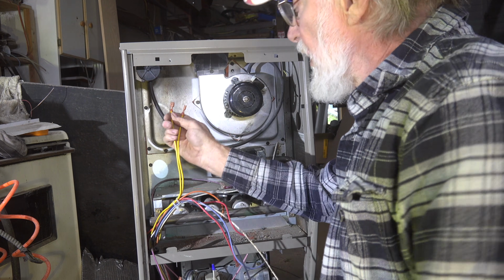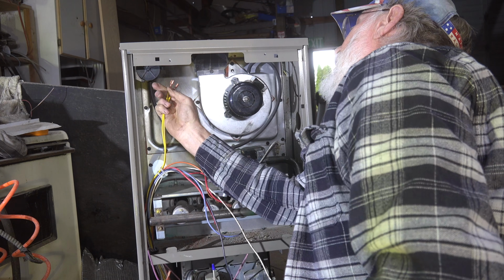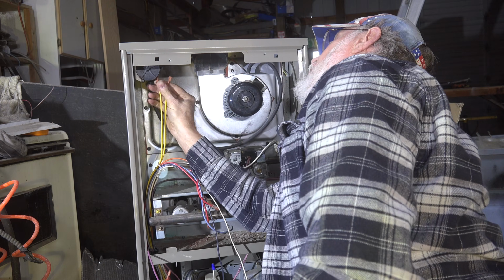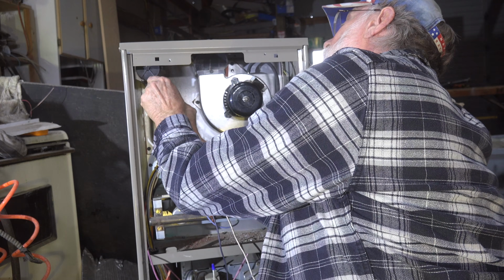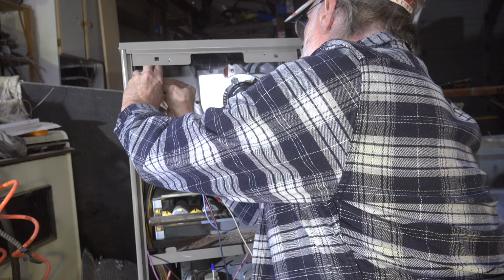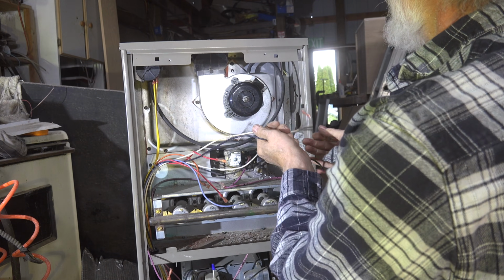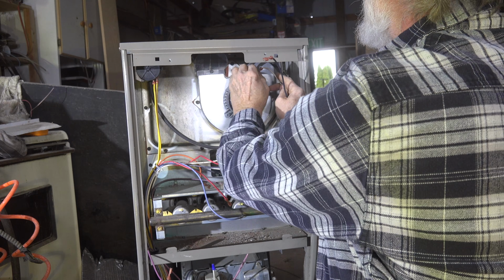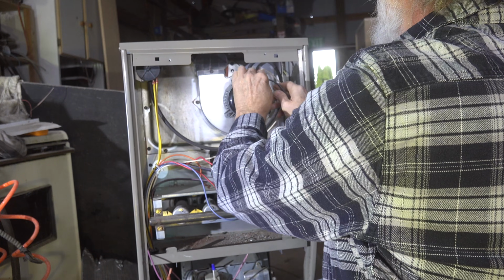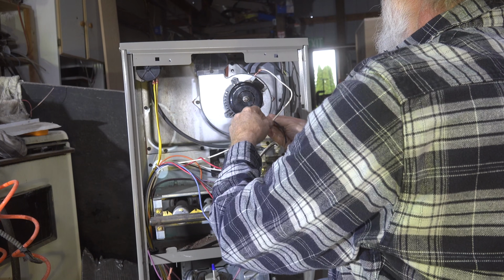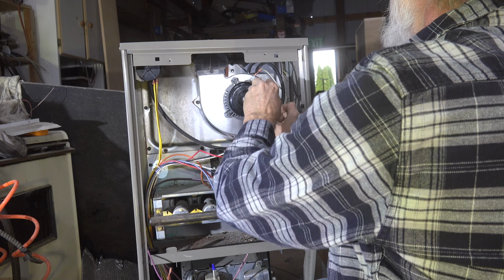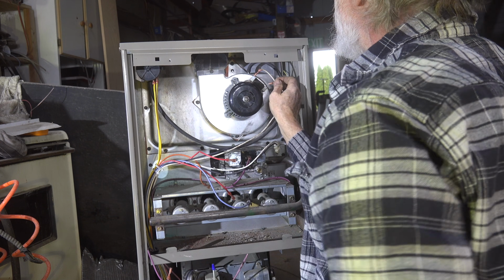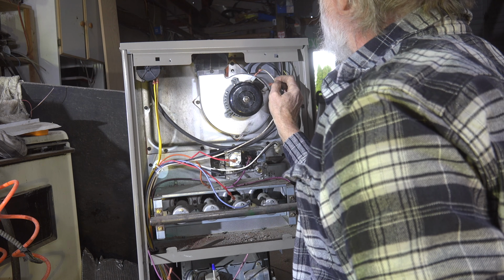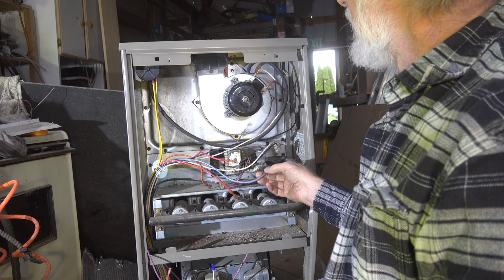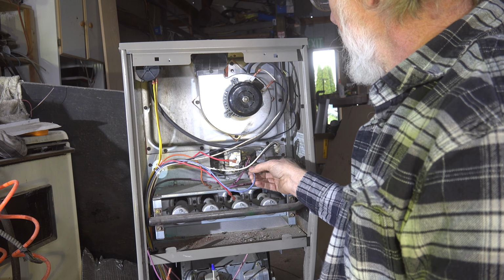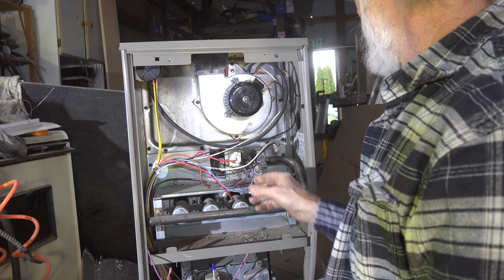The two yellow go to the pressure switch. Doesn't make any difference which one goes where. Black and white, they go to the inducer. Again, it doesn't make any difference which side they go on. Blue goes to the gas valve. Hopefully you did not take any of the other wires off of it.